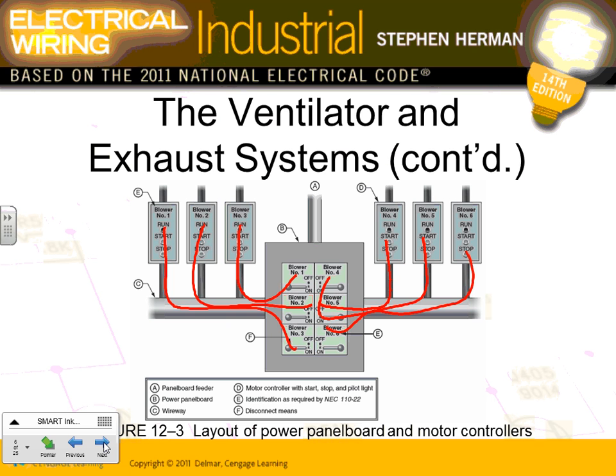I could have fed all of them, my exhaust one, from one feeder and tapped it based on the tap rules. Anybody know what this one is? That's your controller for your exhaust fan. Typically, guys, they have some type of controller so they can control the flow, sometimes speed control, to control how much air they want to exhaust out of the building.